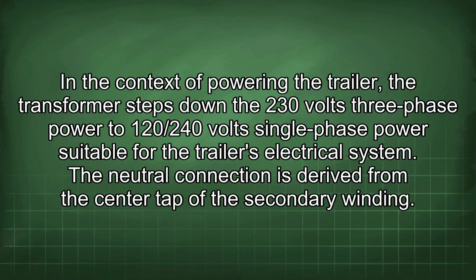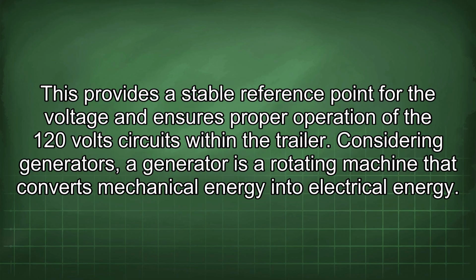In the context of powering the trailer, the transformer steps down the 230 volt three-phase power to 120/240 volt single-phase power suitable for the trailer's electrical system. The neutral connection is derived from the center tap of the secondary winding. This provides a stable reference point for the voltage and ensures proper operation of the 120-volt circuits within the trailer.